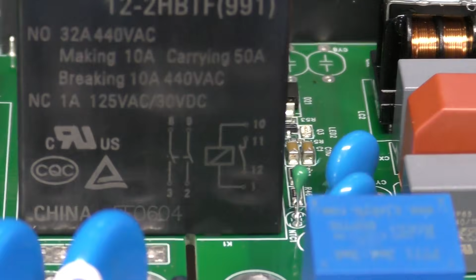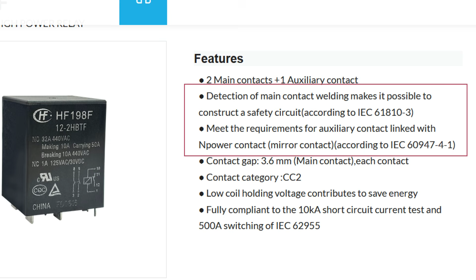Interesting, it looks like it's got some additional auxiliary contacts, so maybe that's some feedback so it can detect the actual state of that output relay, to make sure it's in the state the charger's telling it to be in and hasn't got stuck contacts, for example.